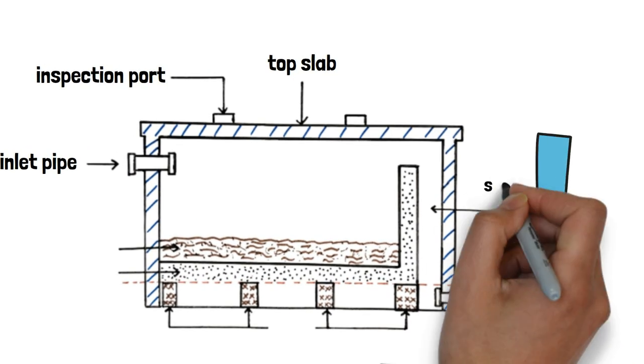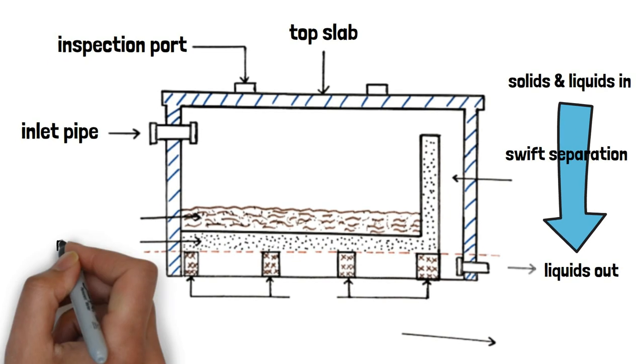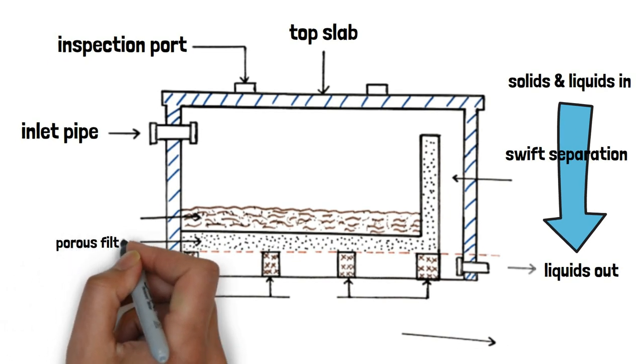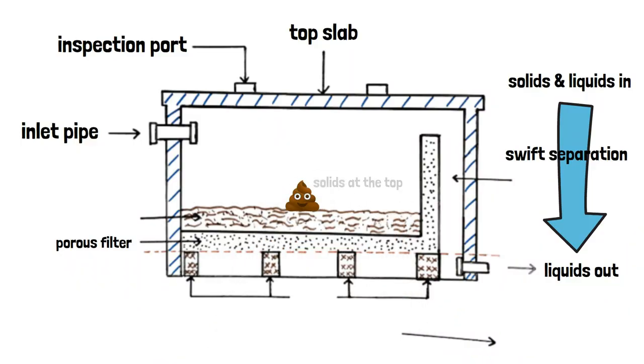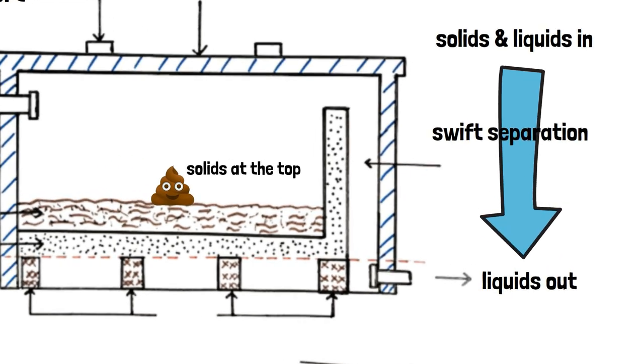a biodigester is meticulously engineered for the swift separation of your excreta from black water. This rapid solid liquid separation is made possible by the biodigester's porous filter. The porous filter is a layer of hollow concrete slabs or ballast porous slabs. The idea here is to hold the solids at the top and have the liquids flow downwards through the porous filter.